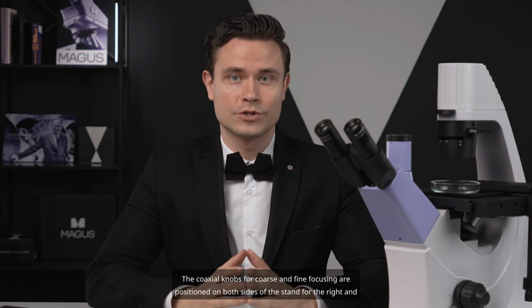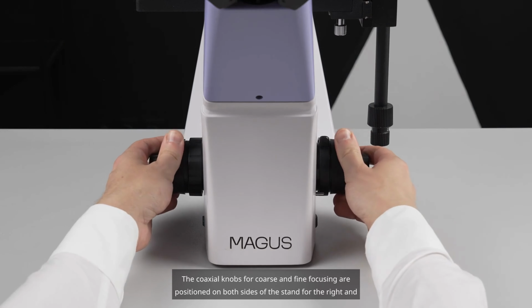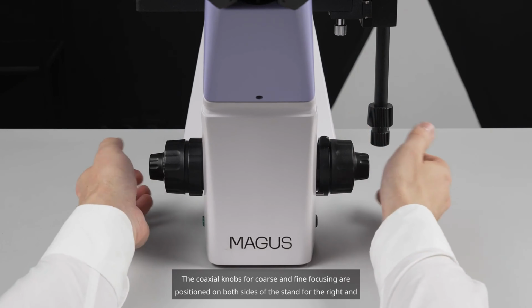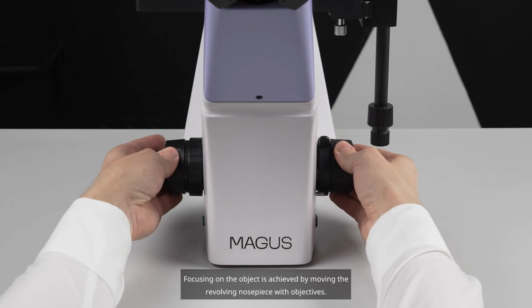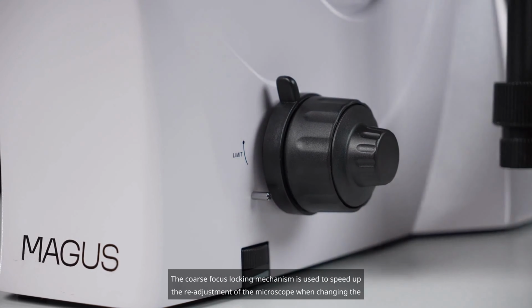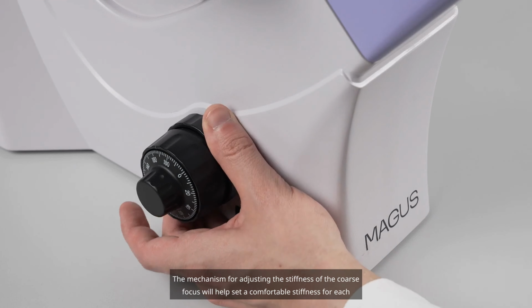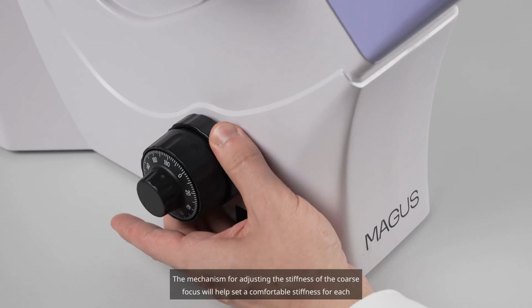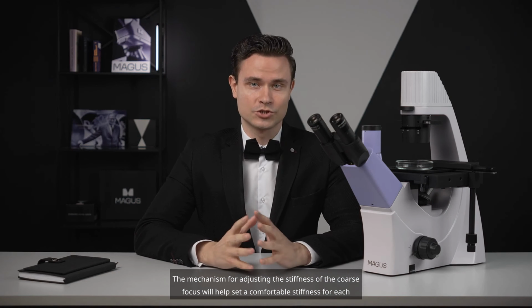Focusing. The coaxial knobs for coarse and fine focusing are positioned on both sides of the stand for the right and left hand. Focusing on the object is achieved by moving the revolving nosepiece with objectives. Fine focusing is required for precise focusing on the specimen and for refocusing the microscope when changing objectives or laboratory glassware. The coarse focus locking mechanism is used to speed up the readjustment of the microscope when changing the object of study. The mechanism for adjusting the stiffness of the coarse focus will help set a comfortable stiffness for each user.